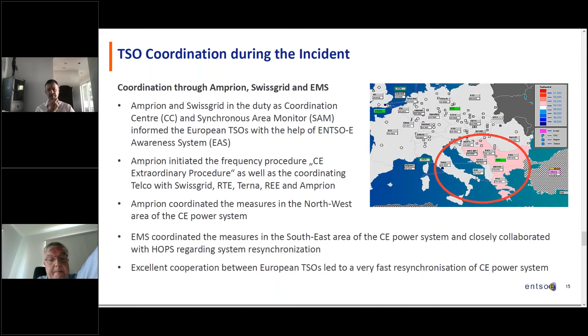The complete cause tree is maybe a bit too detailed, so we put together a less difficult summary. The system separation, in the end, was because of a dynamic angular instability - the angle became larger than 90 degrees. This instability was caused by a very high power flow and a low stability margin in the area, combined with the loss of a first and second event, which together caused the dynamic angular instability.